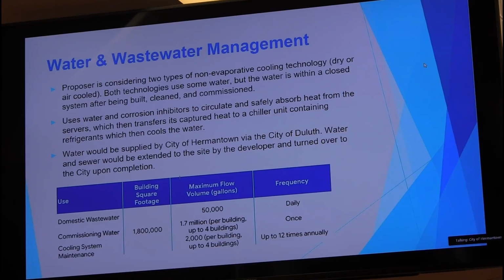In terms of commissioning water, we are projecting 1.7 million gallons to commission the facility. As I mentioned, once we fill that loop, we hope to never have to replace that, and I'll get into maintenance in just a second, but 1.7 million gallons per building, and that is a one-time fill of those closed loops.